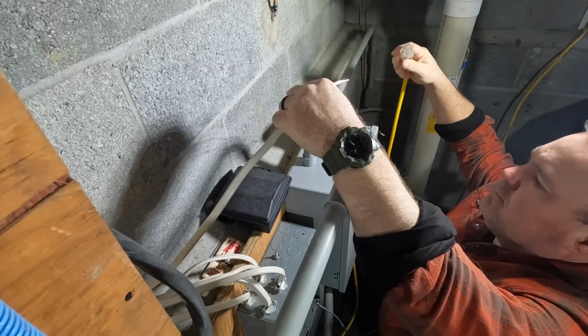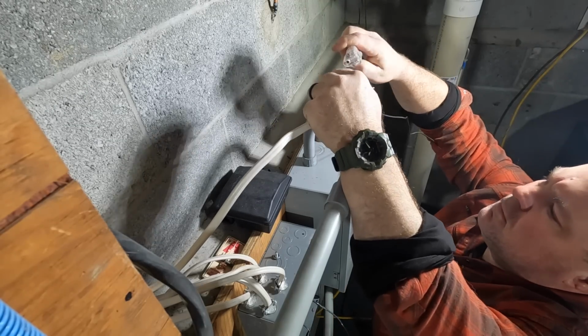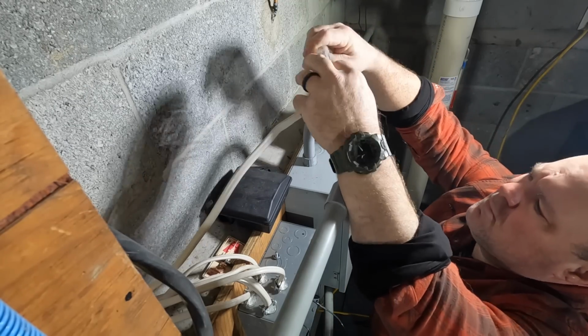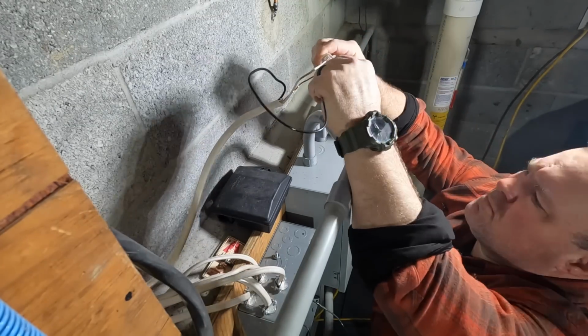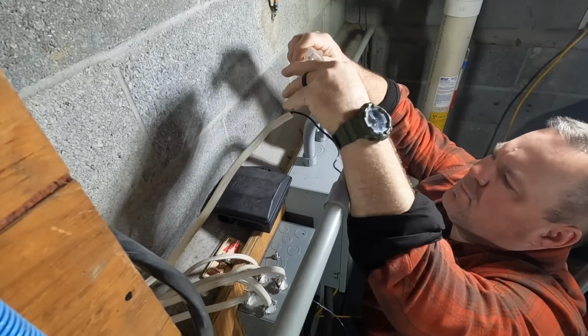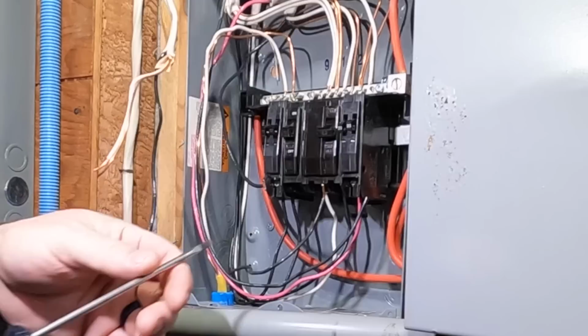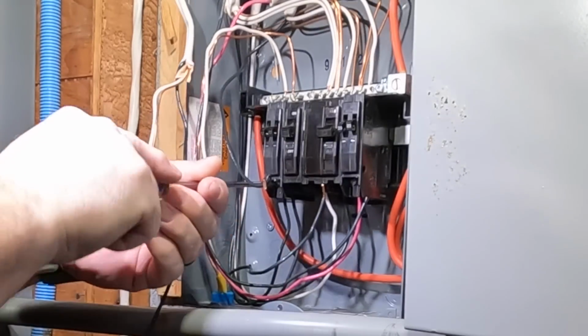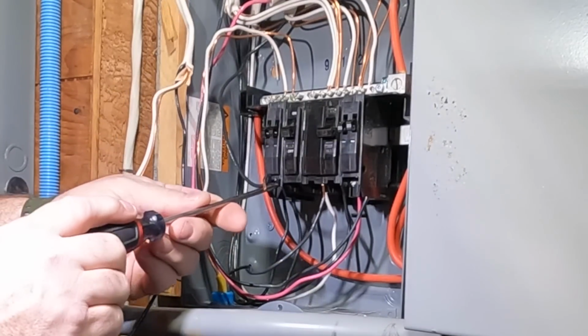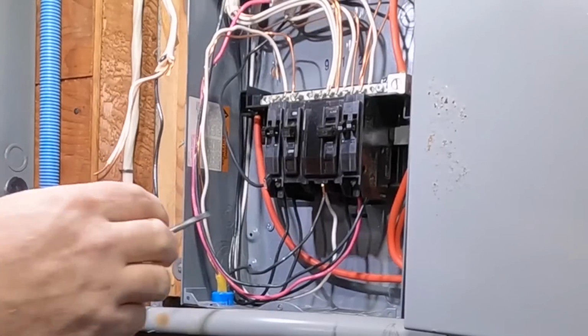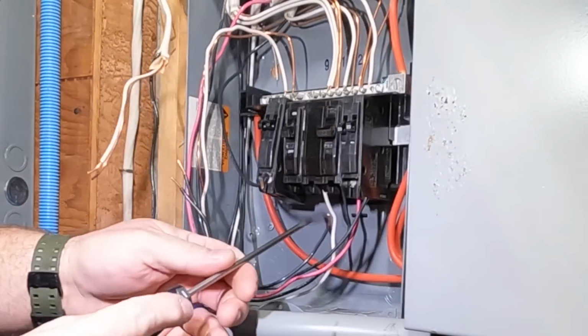But what I'm doing here is I'm going to turn off the disconnect switch for the boiler so that when I connect it to the extension cord, there'll be no load and there'll be no arcing, and it'll be the safest way to do this connection. Obviously, if you don't feel safe doing this, then don't do it. Obviously, this is not something I would do permanently. Obviously, this is just to get some temporary heat while I'm working inside the house so I don't freeze. Like I said, it's about 10 degrees, and we're up in the mountains here. And my customer asked me if I could do this for him.